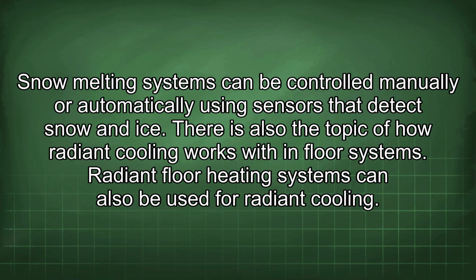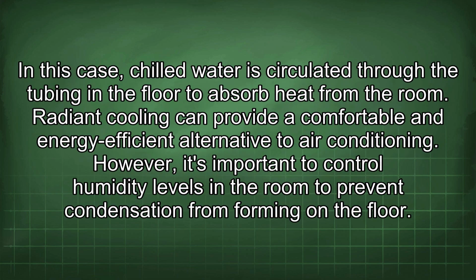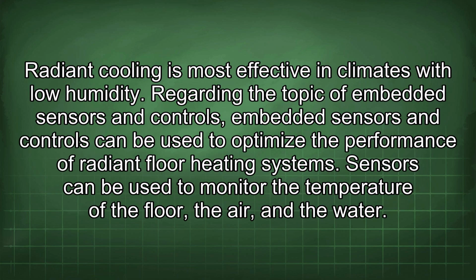There is also the topic of how radiant cooling works with in-floor systems. Radiant floor heating systems can also be used for radiant cooling. In this case, chilled water is circulated through the tubing in the floor to absorb heat from the room. Radiant cooling can provide a comfortable and energy-efficient alternative to air conditioning. However, it's important to control humidity levels in the room to prevent condensation from forming on the floor. Radiant cooling is most effective in climates with low humidity.